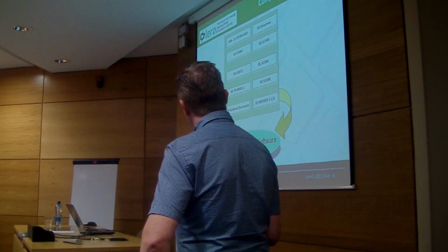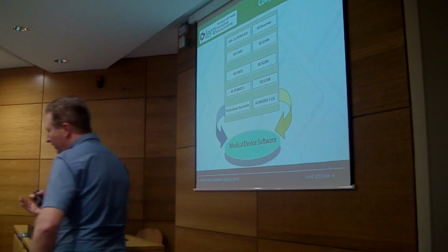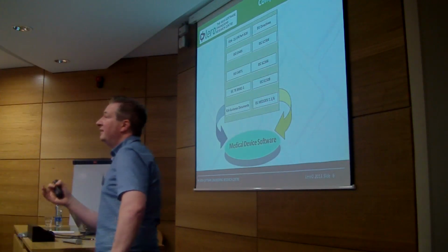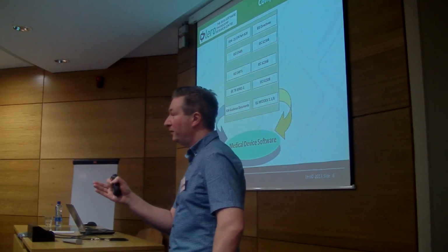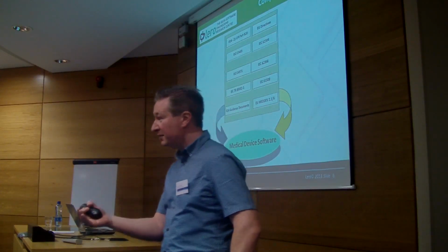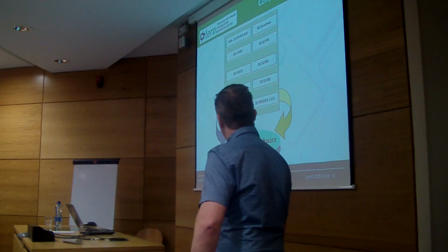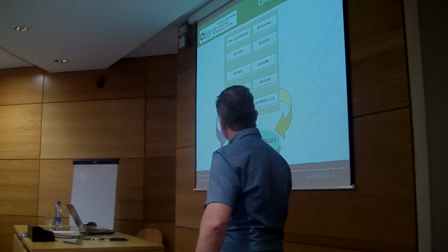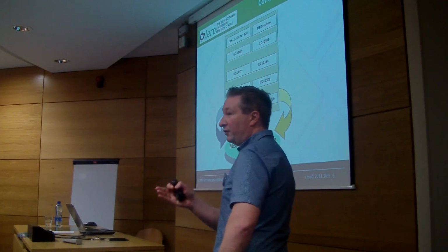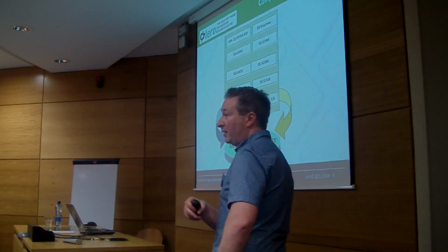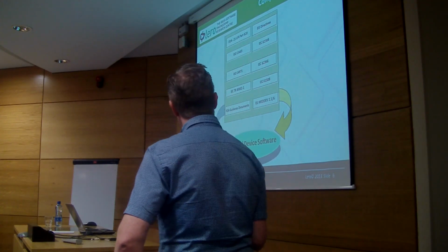What is actually quite useful in this past while is that if you wanted to market a medical device in the US and also in Europe, you had to put 2 different quality management systems in place. One that satisfied the FDA's requirements and one that satisfied the European requirements for quality management systems, which was 13485. Now the FDA will accept 13485 as the quality management system. So at least that makes something a little bit more simple for us.